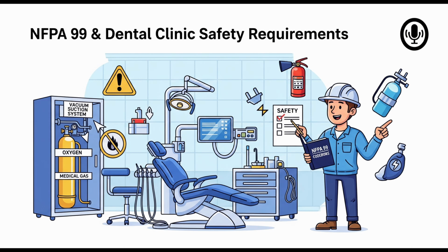While the really detailed specs for Type 1 and Type 2 EES in that section are geared towards hospitals, Category 1 and 2 areas, it lays out the basic principle. An EES has the normal source and one or more alternate sources. If a generator is used, Section 16.5.1.3 says it needs to be installed, tested, and maintained according to another standard, NFPA 110, which is specifically for emergency power systems. Okay, so a full hospital-grade EES might not be required, but some form of reliable backup power is mandated for those specific Cat 3 systems. Correct. The source material does mention components of the EES, like the life safety branch and the critical branch.